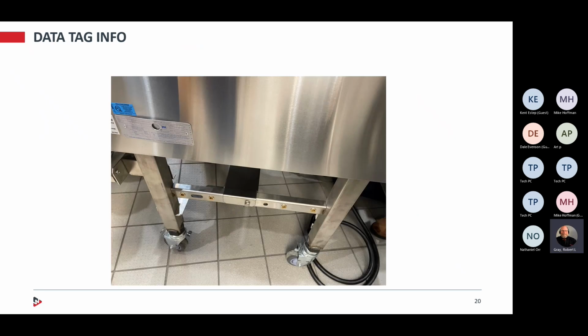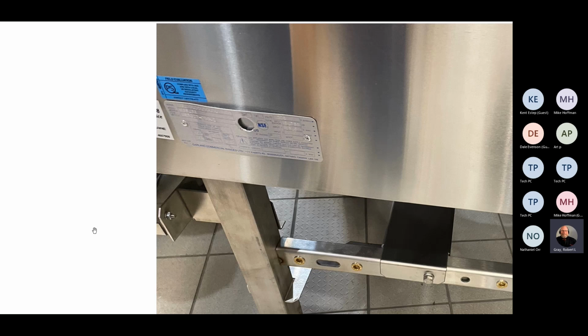Data tag info. Hey guys, we've had a couple calls on technicians that kind of refuse to do the install because of the data tag missing the CSA or the UL labeling. Okay, because it's punched out here. These grills are still technically in a test function, so we haven't gotten the official stamp. However, this blue sticker right here is actually a more intensive testing agency than the UL or CSA. So this blue sticker supersedes the CSA and UL labeling. So as long as that's on there, you're good to install here in North America. Just to keep that in mind. Now, outside of North America, I'm not 100% sure how that's going to work. But inside of North America, we're good to go.